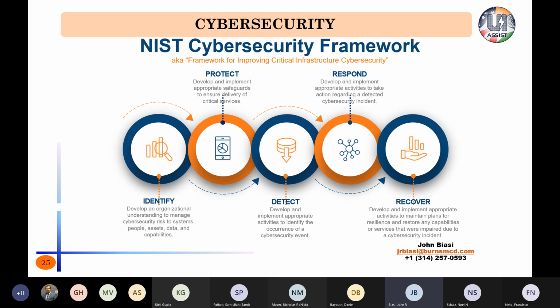One example, like on the previous slide, one of the basic cybersecurity things you want to do is patching, right? Patching is important because it keeps your systems up to date with the most recent version of the code, so that anything found to have a bug or some kind of potential for compromise has been corrected. So you keep that software or firmware up to date, and it keeps you away from potential attackers who could exploit that vulnerability, right? But sometimes there's a trade-off between taking the system offline to patch it and having the system available for use, right? So in some cases, the threat to a device that is protected by multiple layers of security might be outweighed by the need to keep it online, right?